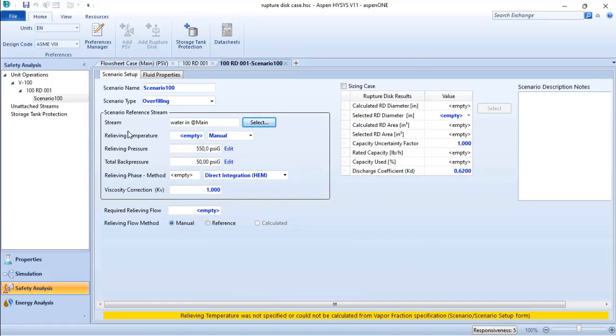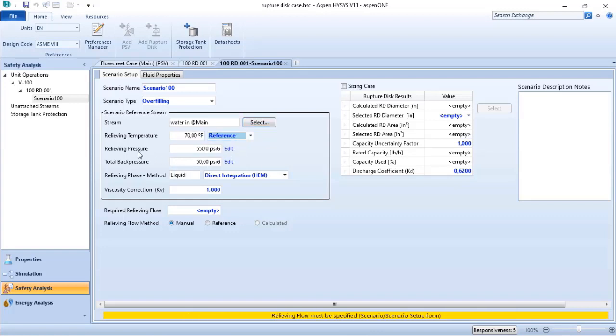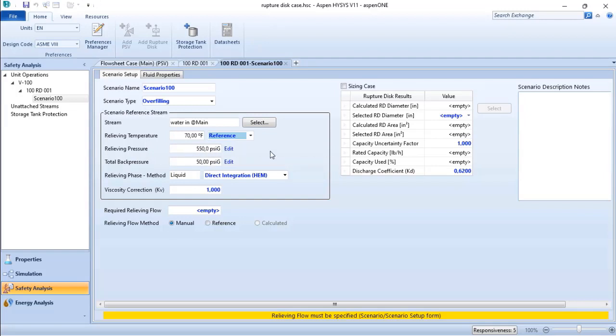I need to set the relief temperature. Here, I don't expect to have an increasing temperature when I have the overfilling of my vessel, so I will use the reference.